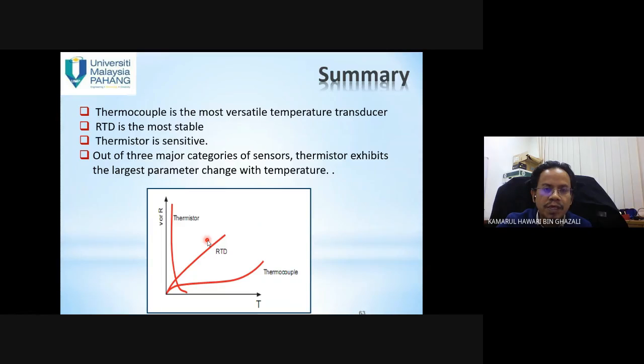So the summary for the thermocouple is that it is the most versatile temperature transducer. RTD is the most stable. Thermistor is sensitive. Out of the three major categories of sensor, the thermistor exhibits the largest parameter change. So this is the comparison of the three types of temperature instrument: thermistor, RTD, and also thermocouple. Okay.